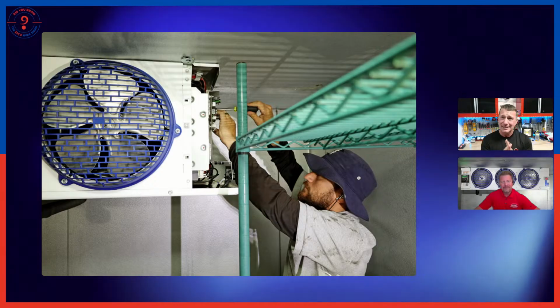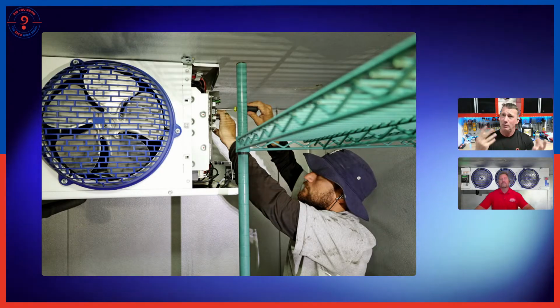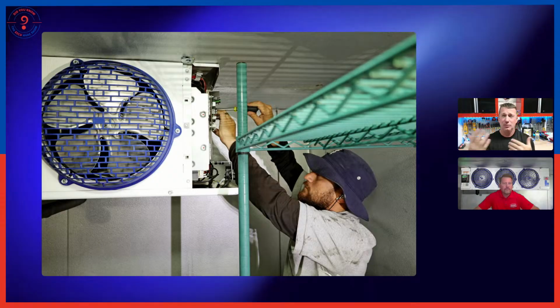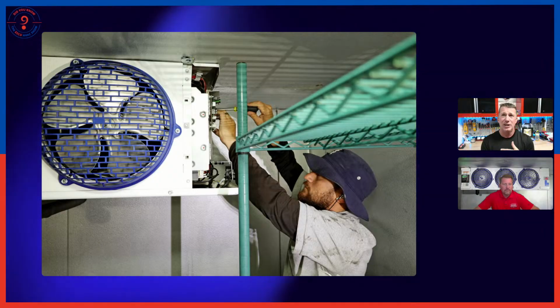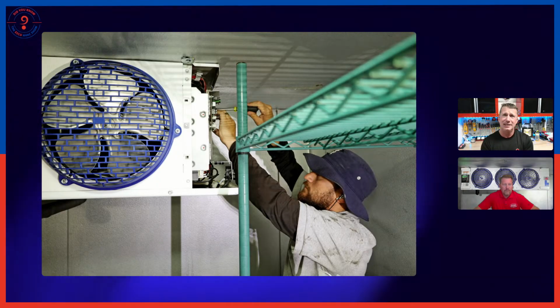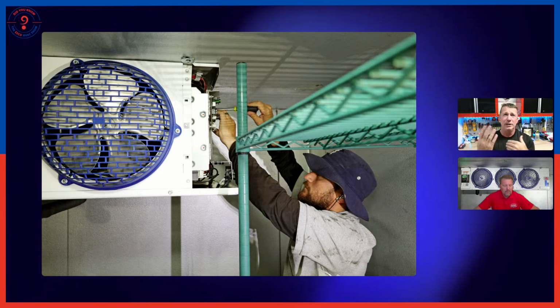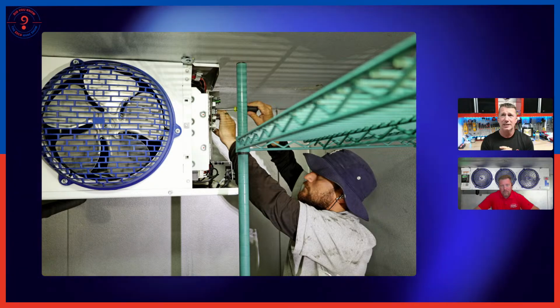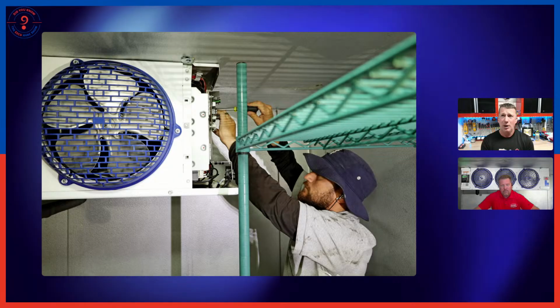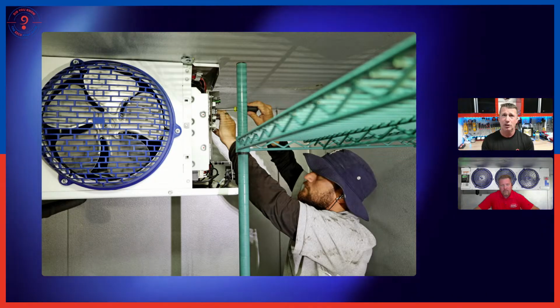So we're going to see some differences, right? But when we start looking at operating pressures, we may have metering device changes, but when we start looking at the capacity of the system, we can comfortably use A1s and A2Ls in the same component. We just make sure that we have the correct safeties on it.